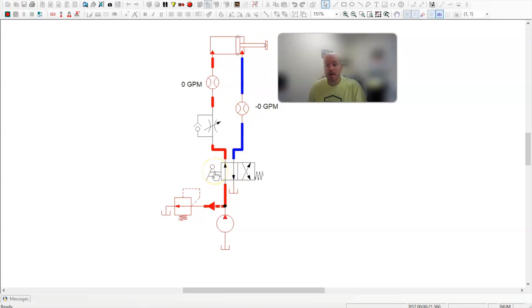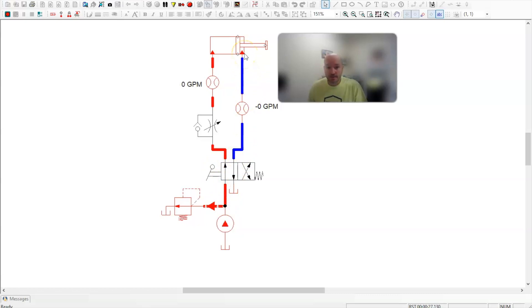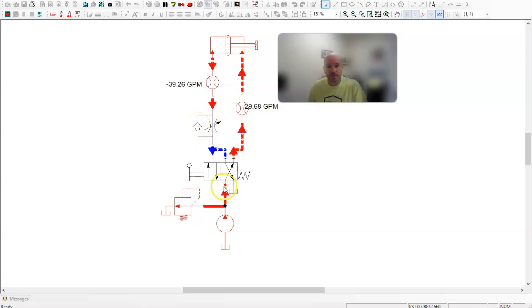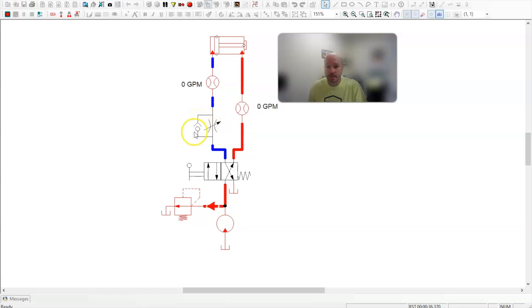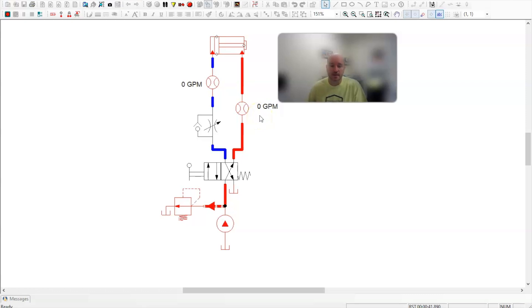Now when I switch this position, oil will flow to the B port on the cylinder and all the oil here will evacuate back through the check valve. So oil flows back, oil came down through here unmetered back down through tank. And you saw there is roughly about 30 gallons. So you can see the difference there.